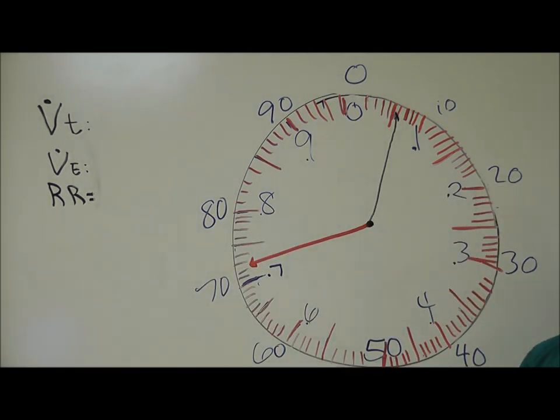Interpreting a Wright spirometer is very similar to interpreting a manual clock. The black hand here is going to be like your hour hand. For our purposes, it represents the liters breathed in that amount of time. The red hand here represents the number of milliliters breathed in the allotted time.